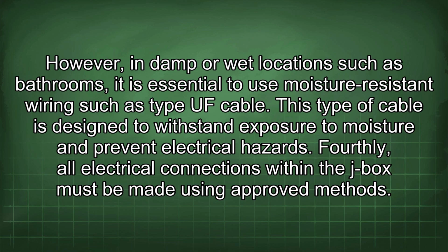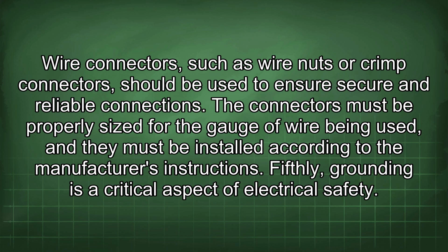Fourthly, all electrical connections within the J-box must be made using approved methods. Wire connectors, such as wire nuts or crimp connectors, should be used to ensure secure and reliable connections. The connectors must be properly sized for the gauge of wire being used, and they must be installed according to the manufacturer's instructions. Fifthly, grounding is a critical aspect of electrical safety.